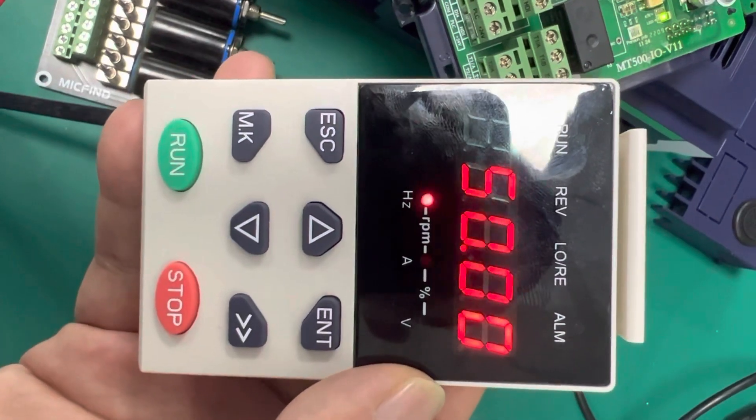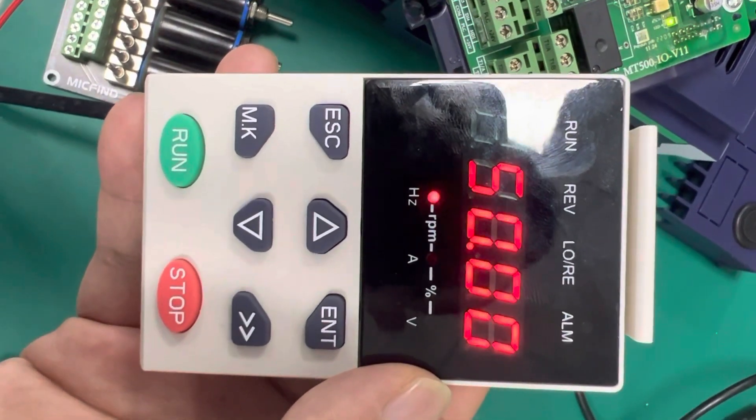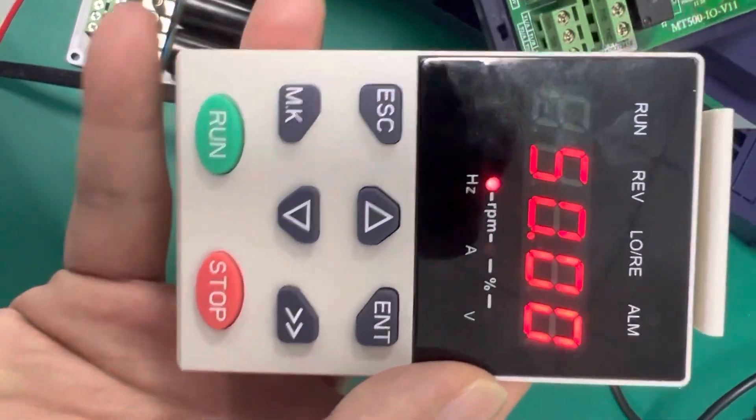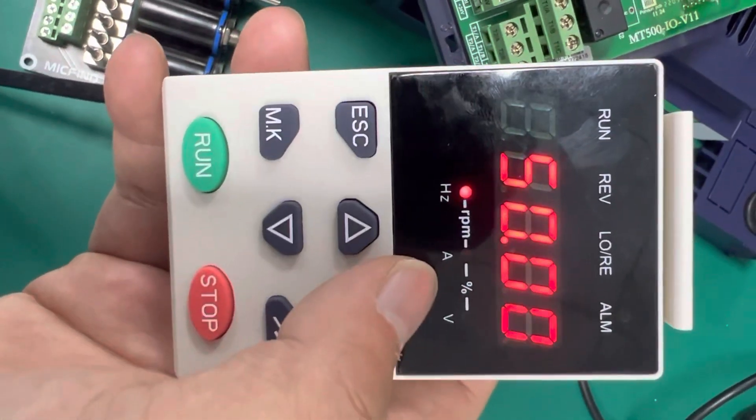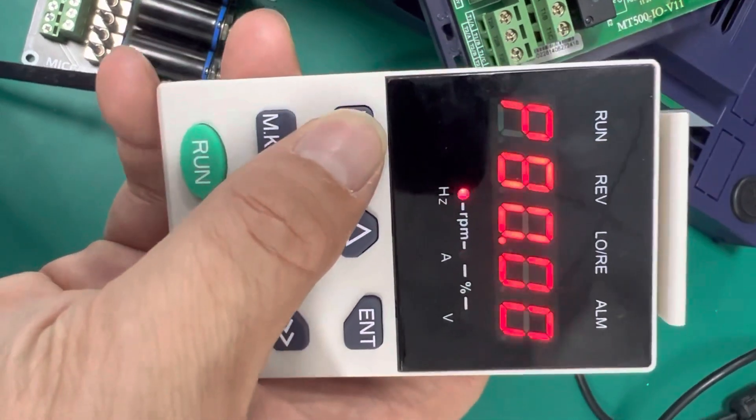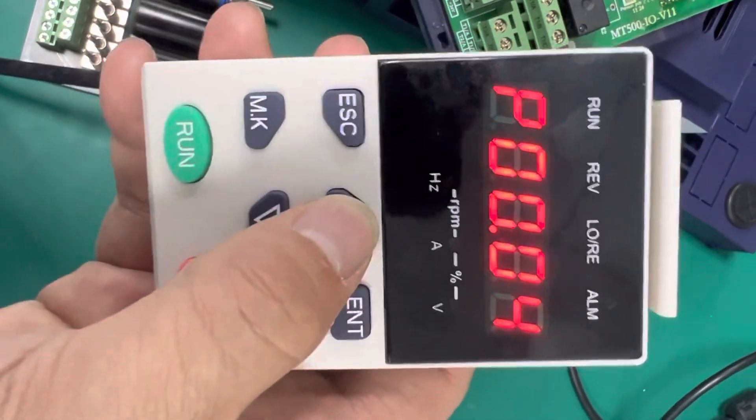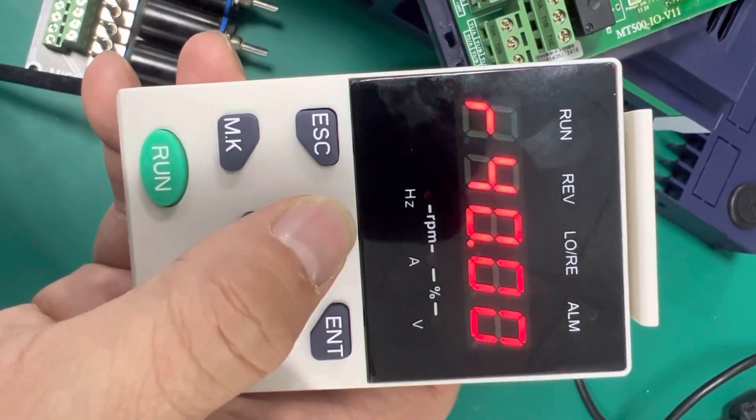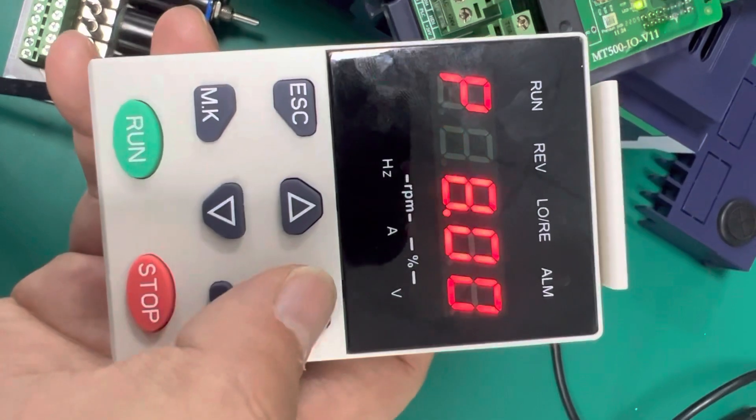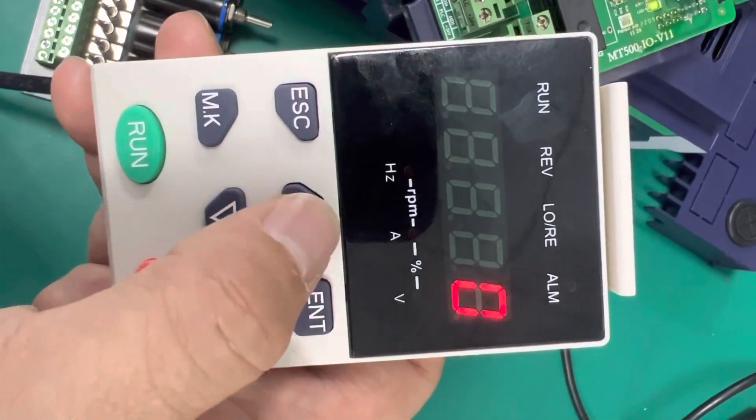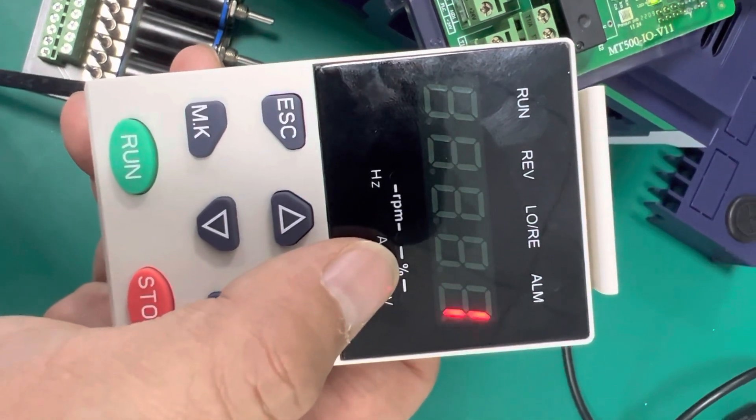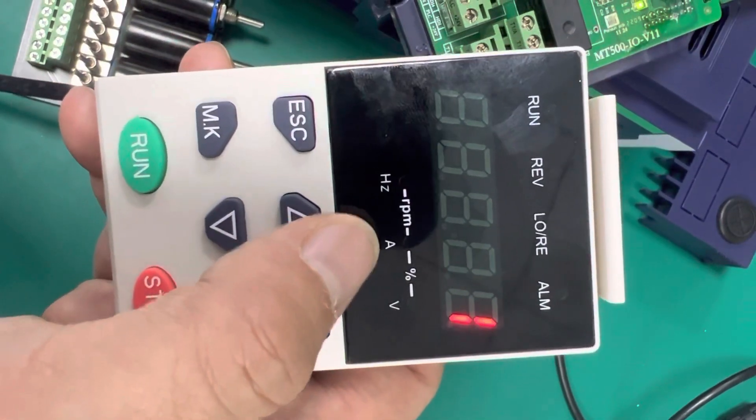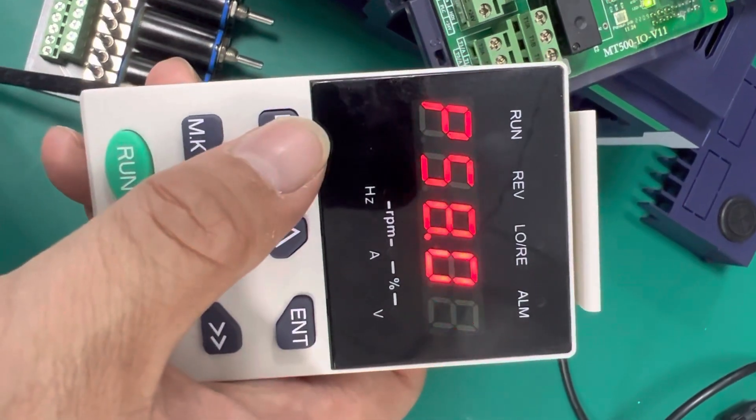Hi guys, let me teach you how to use our VFD 500 fire mode operation. First, we need to activate and enable the fire mode so we can see the parameter 58.00 and set it to 1. This means the fire mode has been activated and enabled.